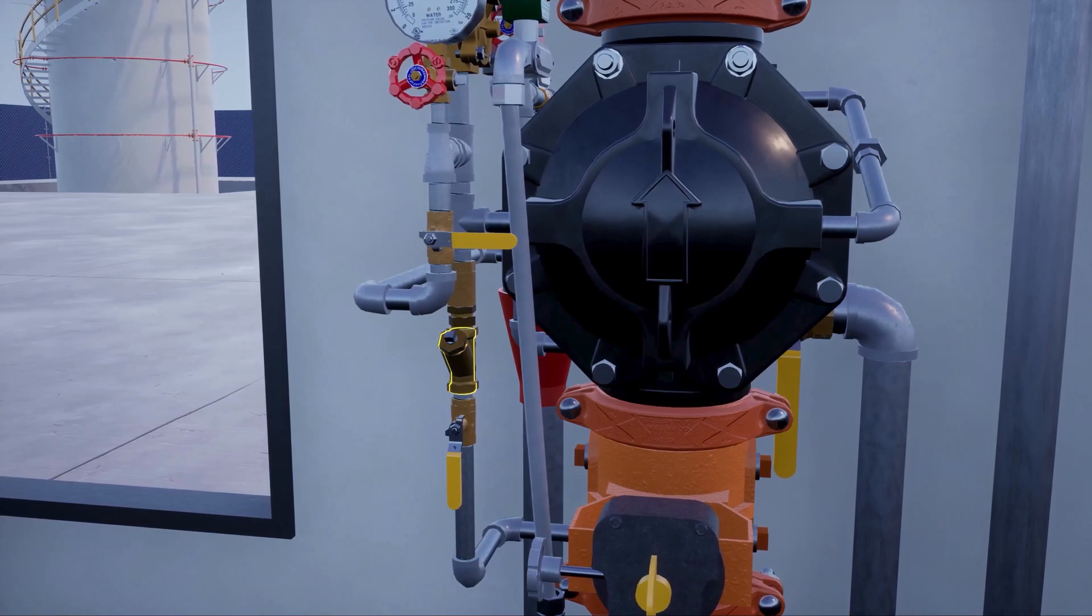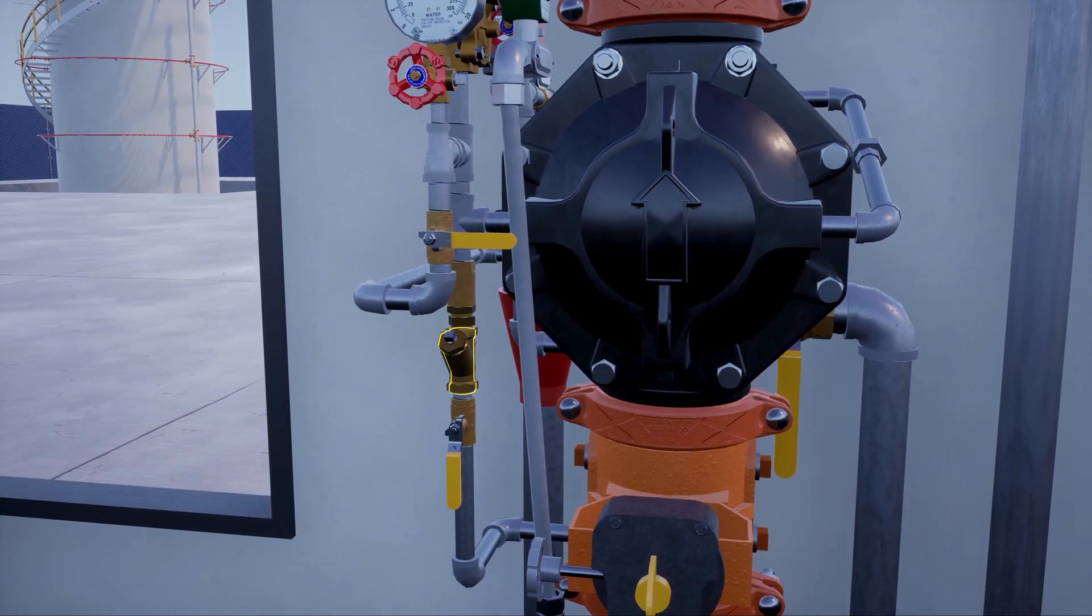The Y strainer keeps debris from entering the restricted orifice. The restricted orifice reduces the rate at which water can enter the prime chamber, ensuring that prime water will drain faster than it can be supplied.